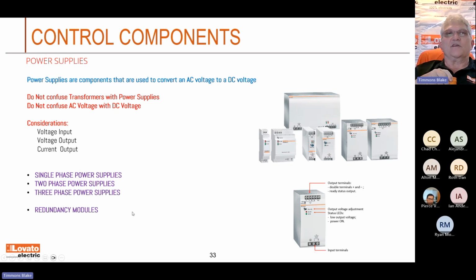Well, I can use these redundancy modules and put two of them and get the 40 amps with two 20s. Basically, all it is is a back-to-back diode. So if one power supply goes out, or the little ripple that I mentioned earlier is out of sync, it keeps the regulators from fighting each other. So you can put this little back-to-back diode between two different power supplies and get your 40 amps without harming, without overheating the devices.